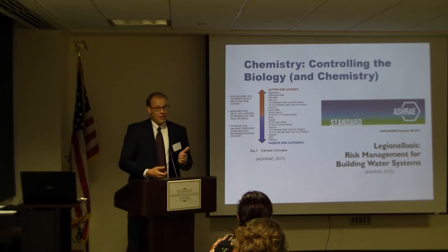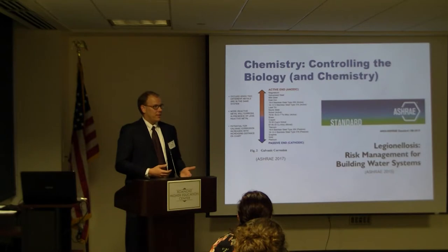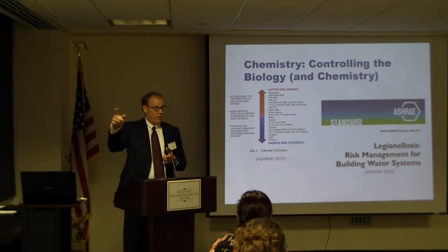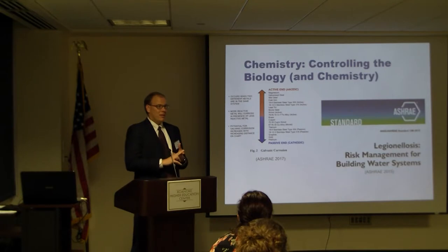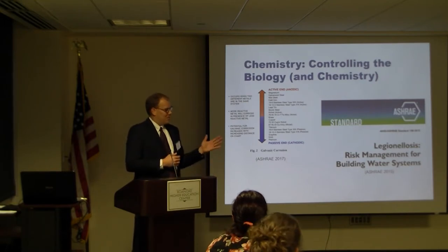I don't have a nice psychrometric chart, I had that conversation earlier. If you look at the Weather Channel, you look at all these data for what the temperatures are, there's two components to temperature. There's dry bulb, which is kind of what's read on every thermometer everywhere, right? Then there's the wet bulb temperature. We need two points to define the energy of air. We need to know what is sensible, which is really just what you read on a thermometer, and what is the humidity content of the air. Those two points will give you what the energy of the air is and how much it's going to take to change the property of that air. So a cooling tower will cool it down.